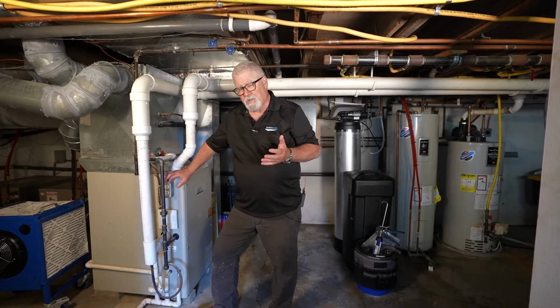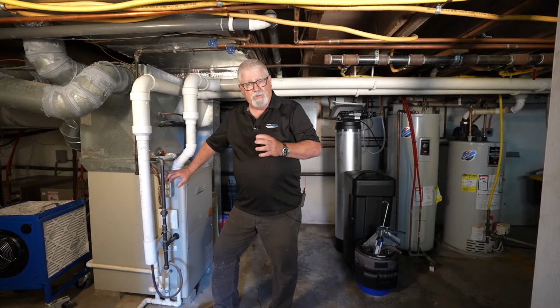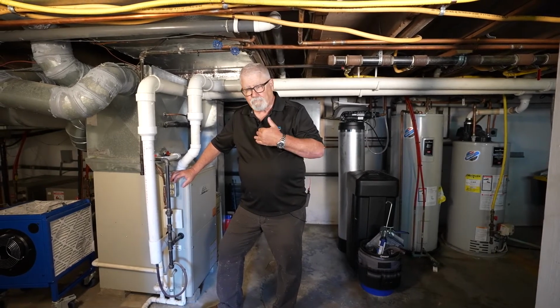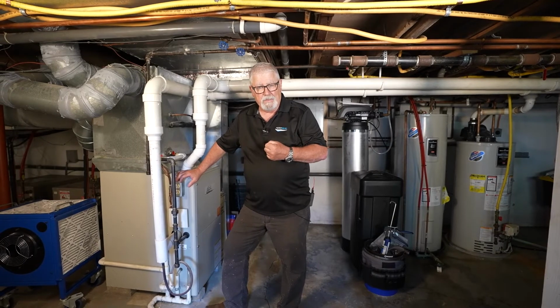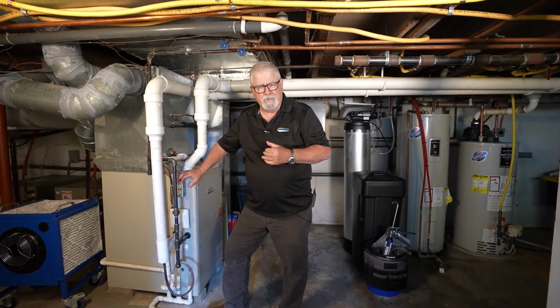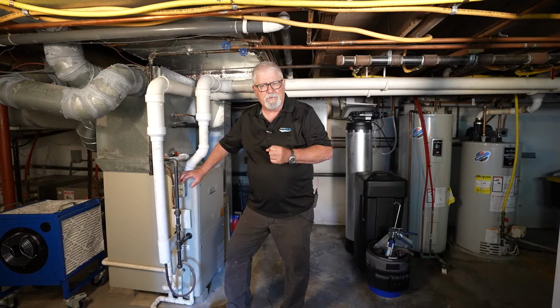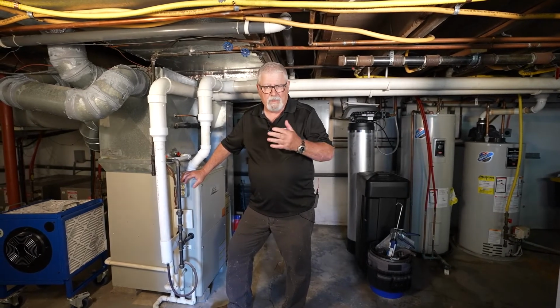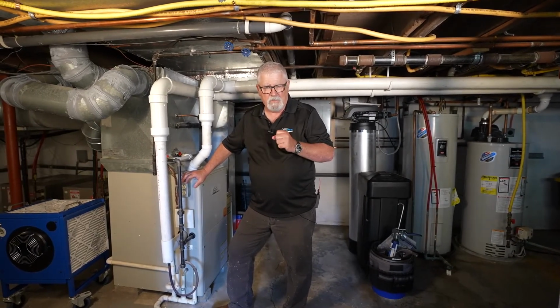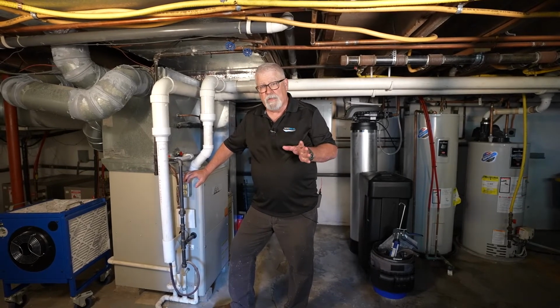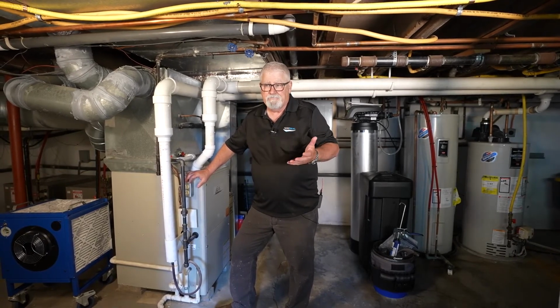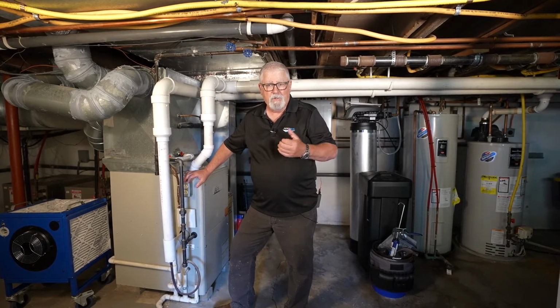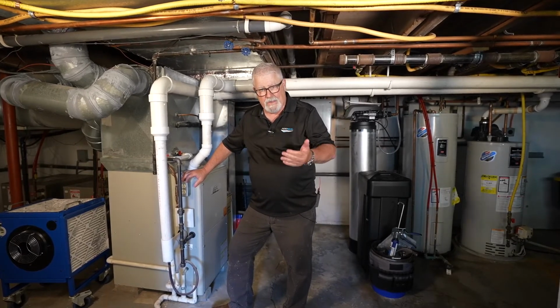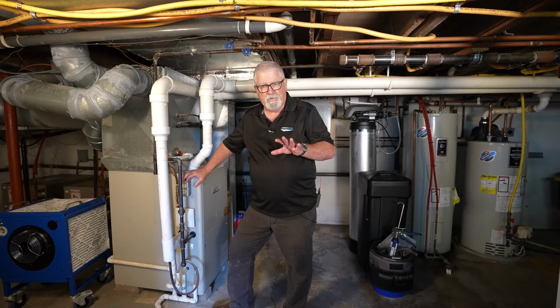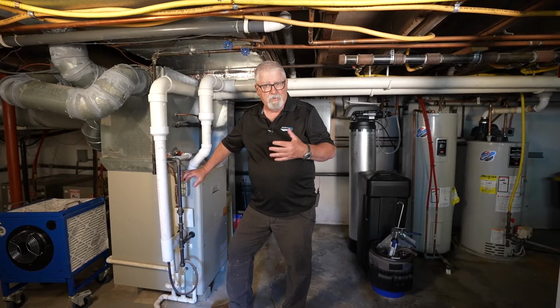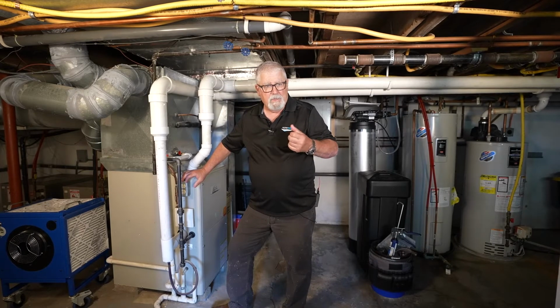Now our supply side was not really all that bad, but we had 27 square inches of duct leakage on it. So we went ahead and sealed the supply side up. Had to do a little hand sealing here and there because of some sizable gaps in it. But overall, we were able to get that down. We got that a little bit under 5 square inches of duct leakage as well. So overall, we're really, really happy with this job. We took it down from basically 150 square inches. We got it down to 10 square inches, both supply and return. And now we're going to have a very satisfied customer, and we're not going to have any issues with any of the outside air coming in.